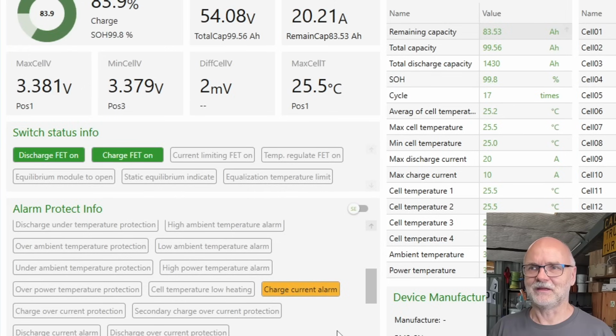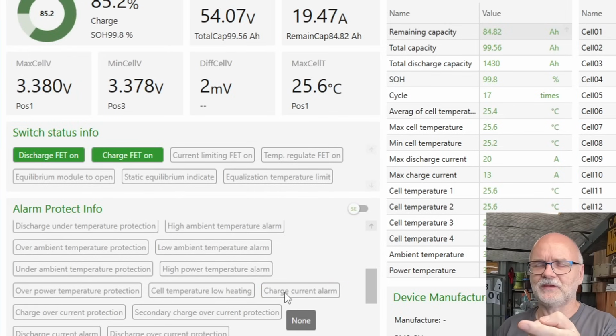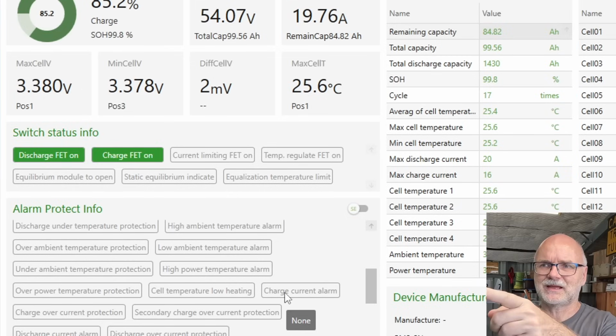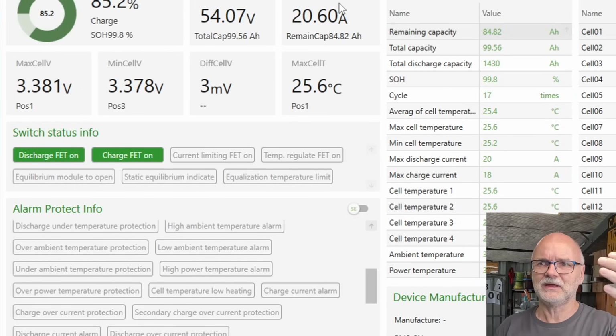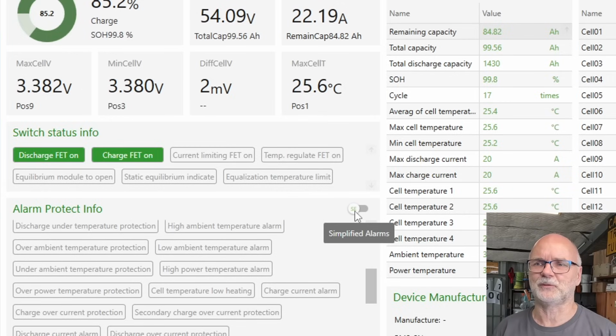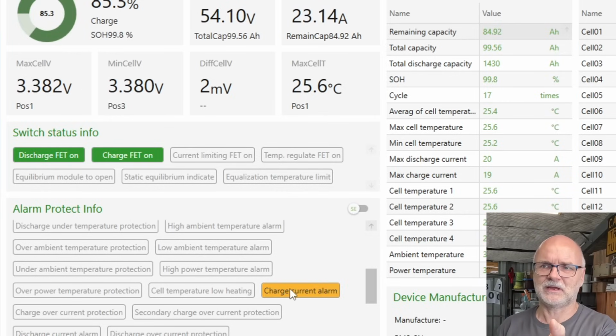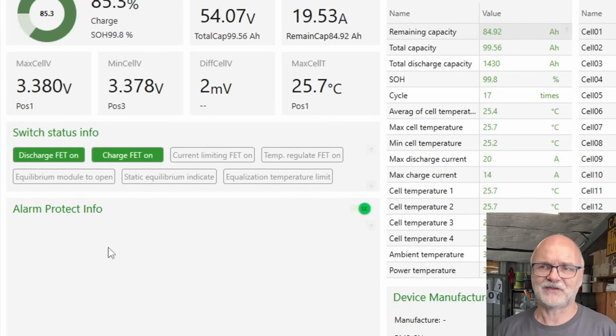Come on, go under 20. Just to recover, now we are under 20 amps. It clears the alarm. Current increases now to 23. Alarm kicks back in, but it doesn't show unless you hit this little toggle switch here. Watch, 23, here comes the alarm again. But if you toggle this switch, you can't see any alarms.